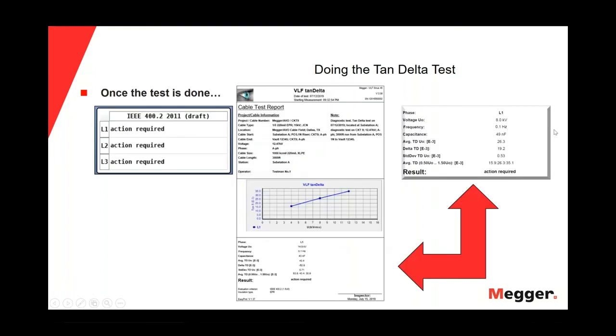And also, once the test is done, we will get the result of the tan delta test, in this case, action required, a complete report with the important information in there. In this case, we are seeing only the phase L1, the graphic of the phase L1 and the result of L1, but of course, we can have in one report the result for the three phases, okay? And of course, we will see the more important information as the average of the tan delta, the delta of the tan delta, and the standard deviation.